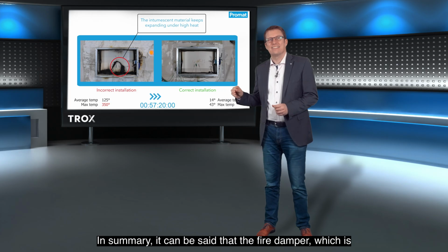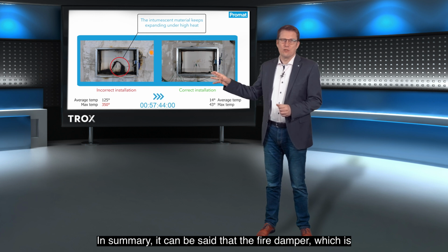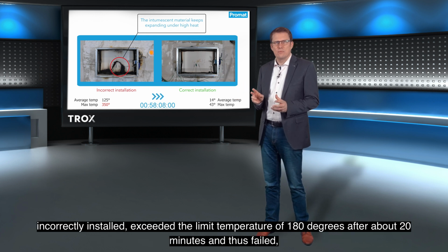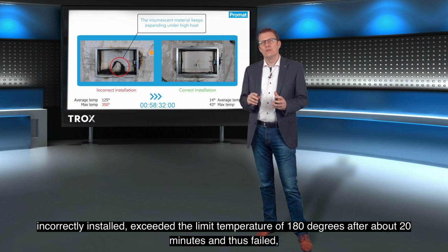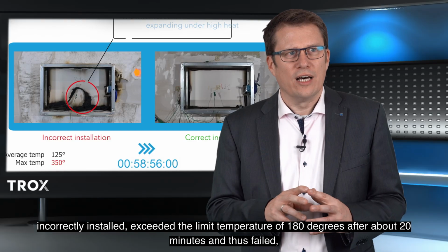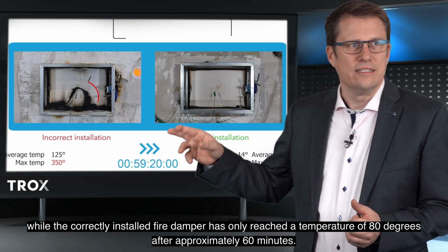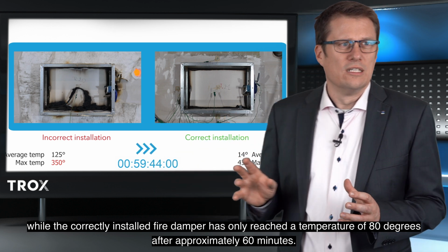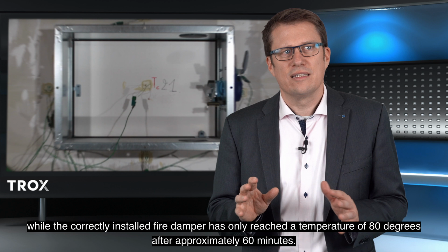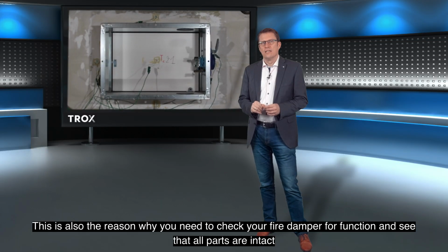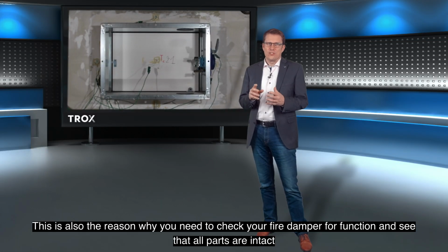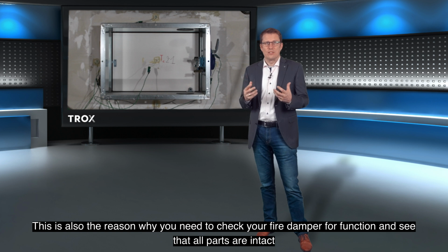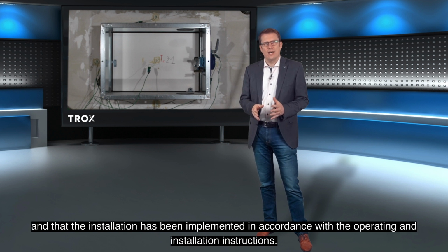In summary, it can be said that the fire damper, which is incorrectly installed, exceeded the limit temperature of 180 degrees after about 20 minutes and thus failed, while the correctly installed fire damper has only reached a temperature of 80 degrees after approximately 60 minutes. This is also the reason why you need to check your fire damper for function and see that all parts are intact and that the installation has been implemented in accordance with the operating and installation instructions.